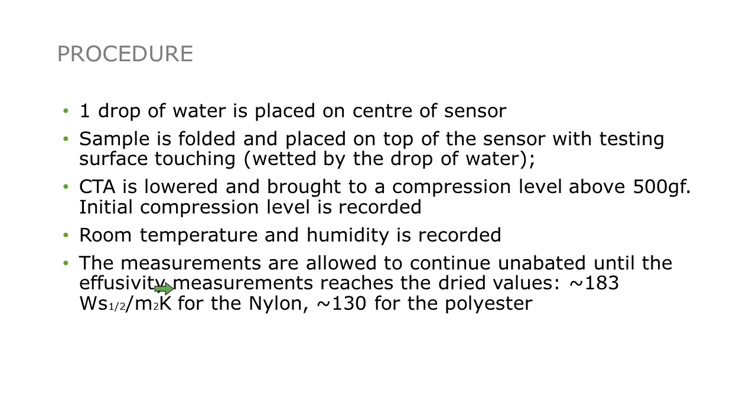And it is suggested to let the measurements go for quite a while. I think the test time was over a half hour. I think it may be as long as an hour or even longer in duration, if you really want to look at the overall drying profile of what it looks like.